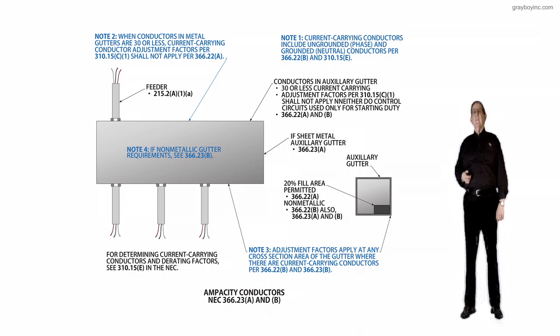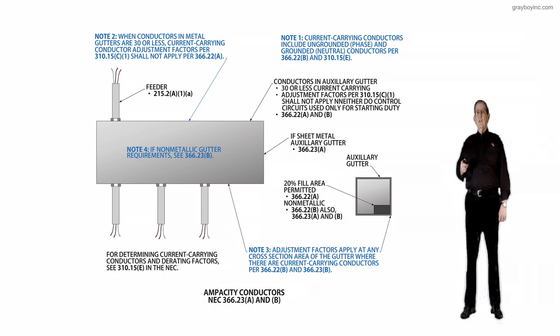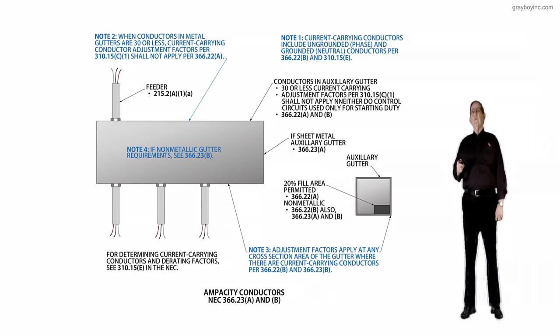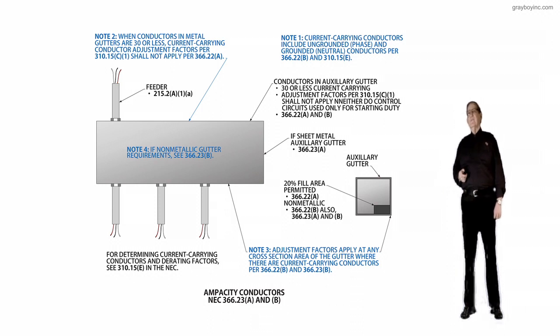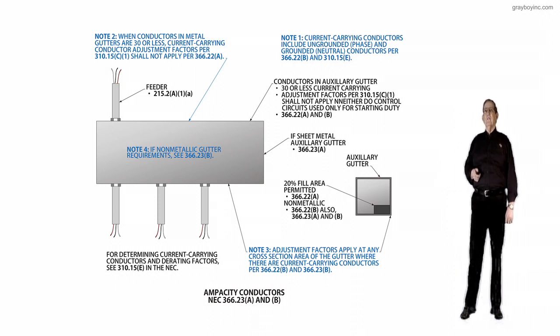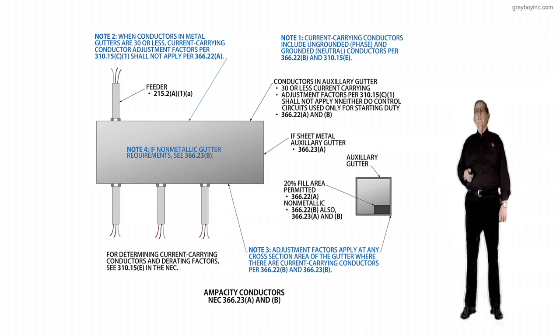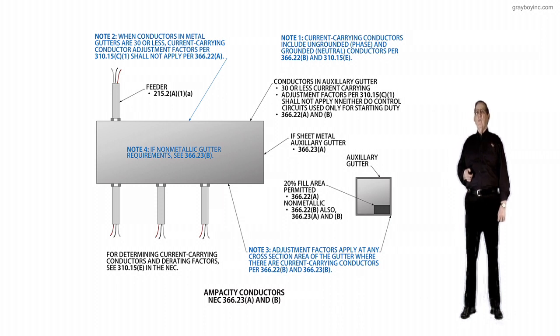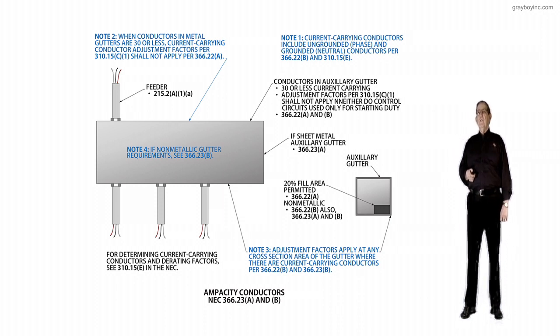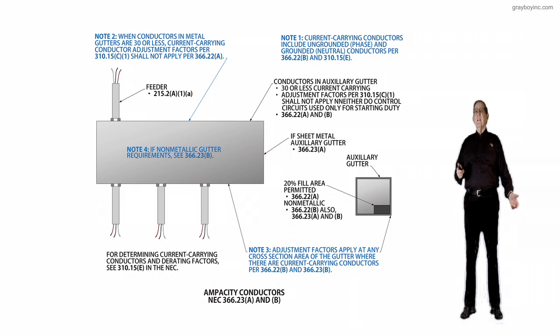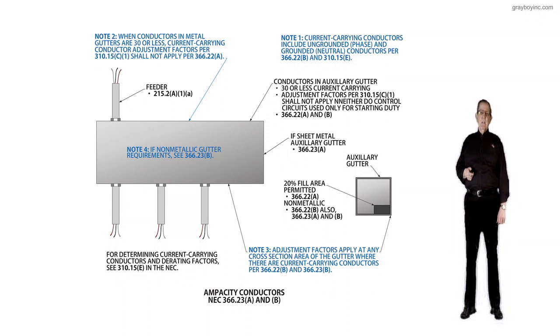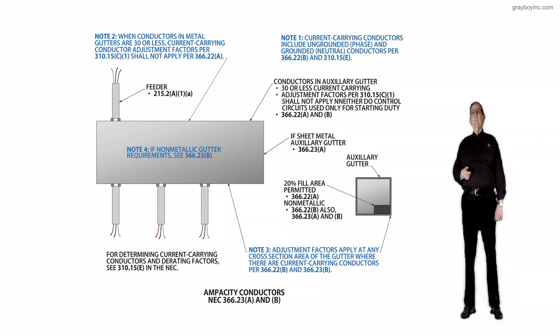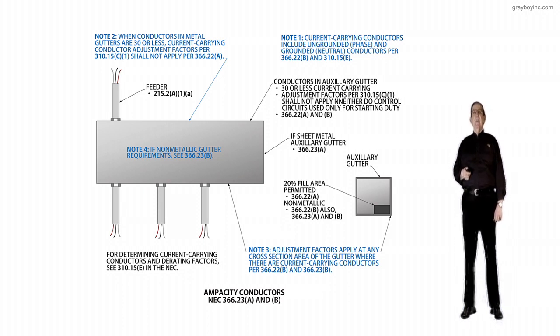Now, the next thing I would like to review is the notes. Note 1 to the right at the top of the illustration states current carrying conductors include ungrounded phase conductors and grounded neutral conductors as outlined in 366.22B and 310.15E.